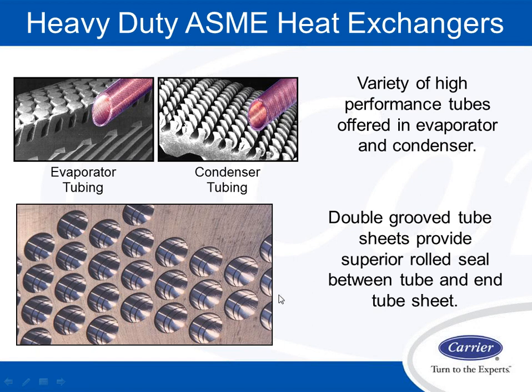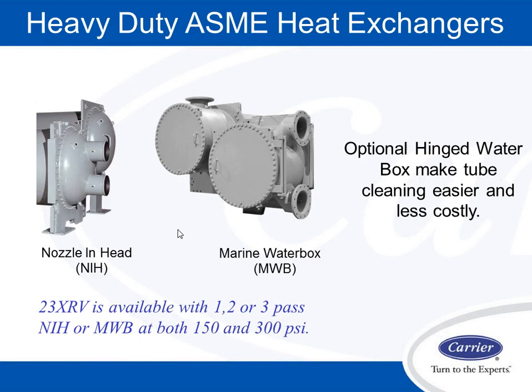There are manufacturers that produce their tube sheet with only a single groove. There are some that just provide epoxy coating to properly put the tubes in the tube sheet. We use a double grooved tube sheet to provide a superior fit and a very tight seal between the refrigerant and the water side. Nozzle-in-head marine water boxes are options you can get.